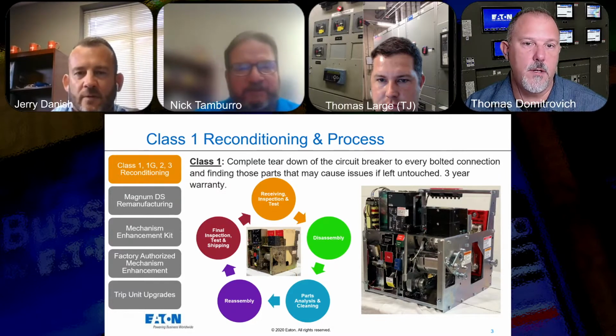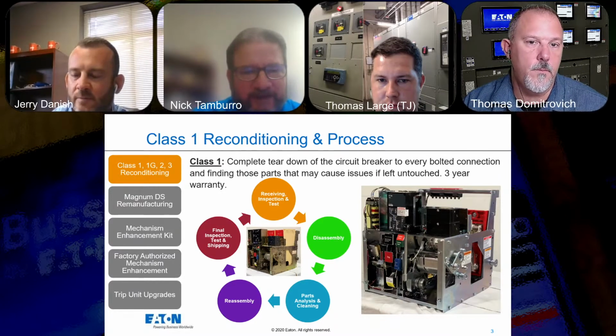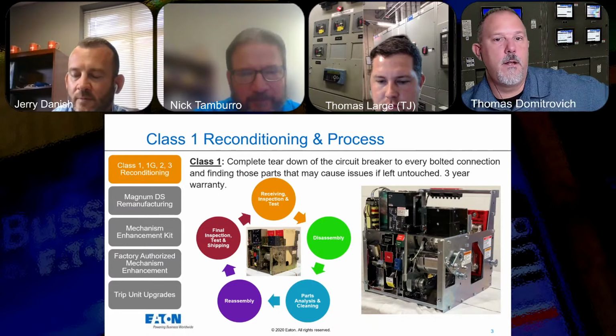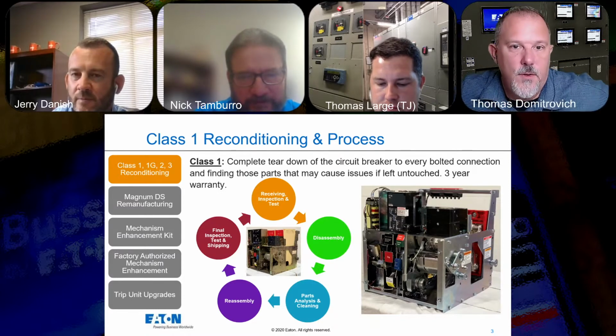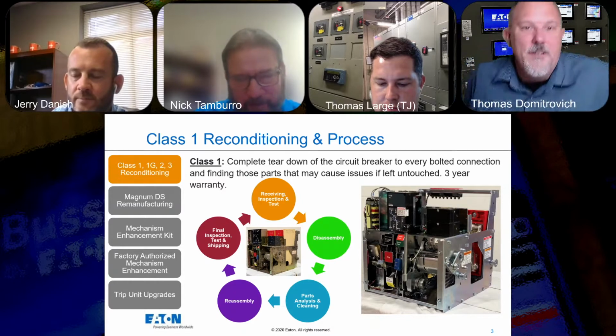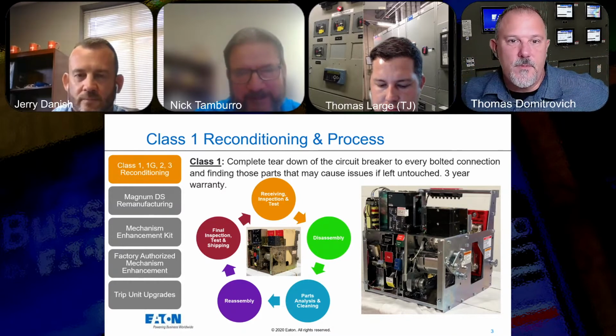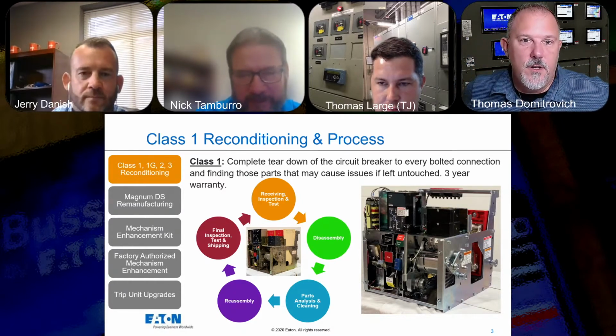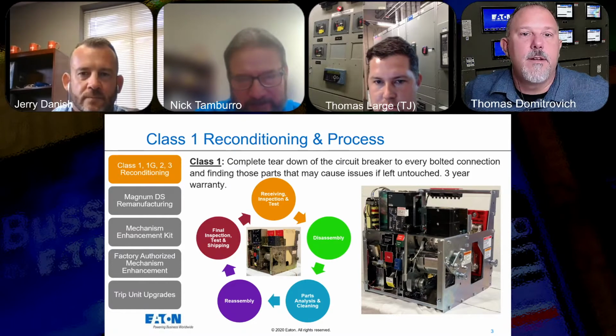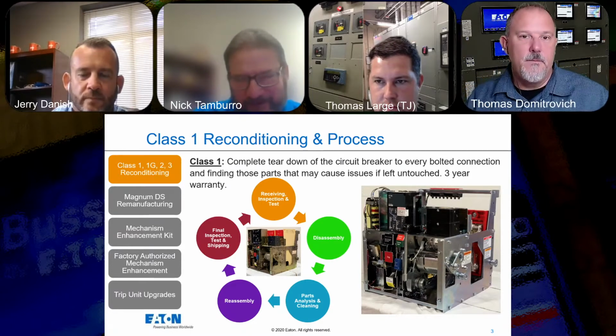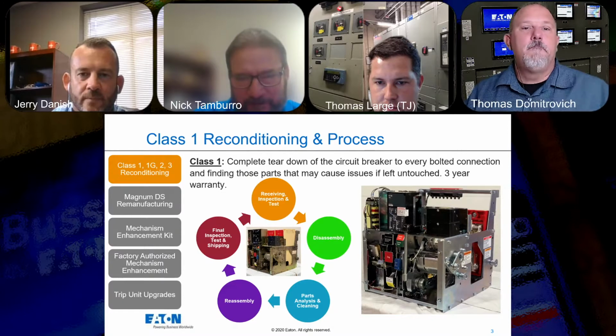That's why I did mention we measure contact resistance, as in micro ohm level of the contacts when the breaker's closed, to see before and after the condition of the breaker. So it might come in with 60 microohms and go out with 18 microohms. Okay, gotcha, and that's just from the cleaning of the contacts. Residue builds up over time.